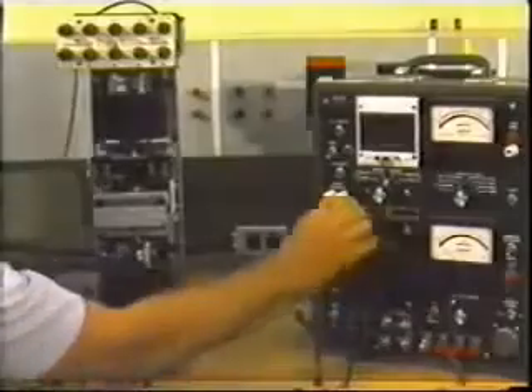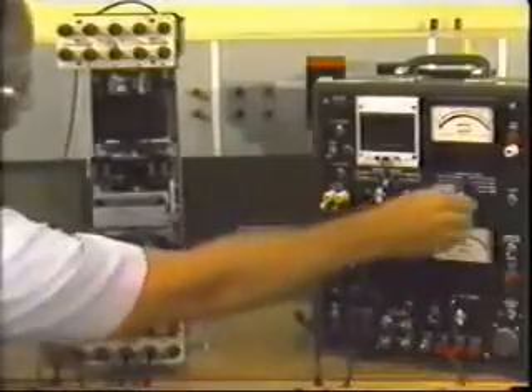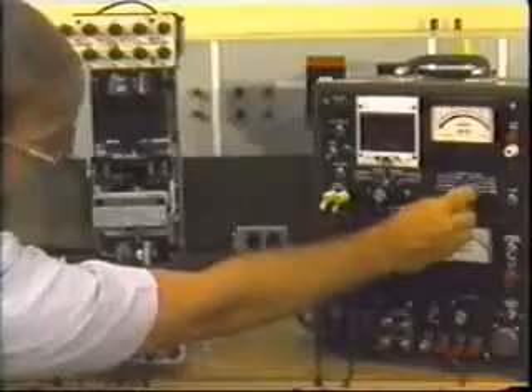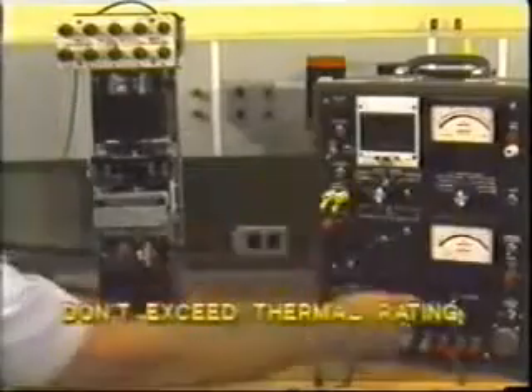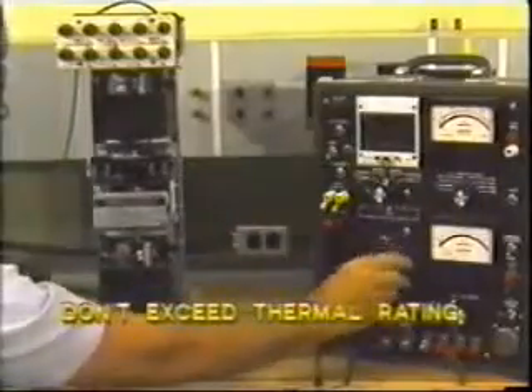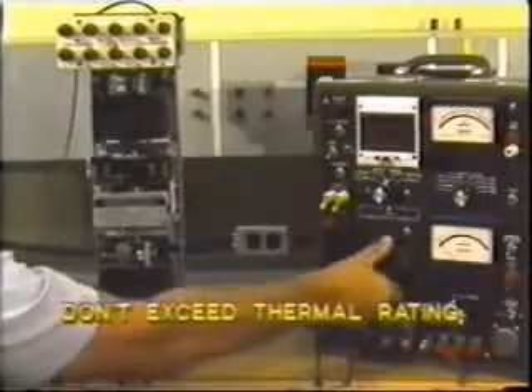It has been proven that a relay's useful life is limited by accumulative thermal duty. This is mainly due to periodic testing rather than from actual power system faults. Make sure that you know the thermal rating from the instruction manual of each relay under test. Keeping these considerations firmly in mind, let's look at relay test sources.